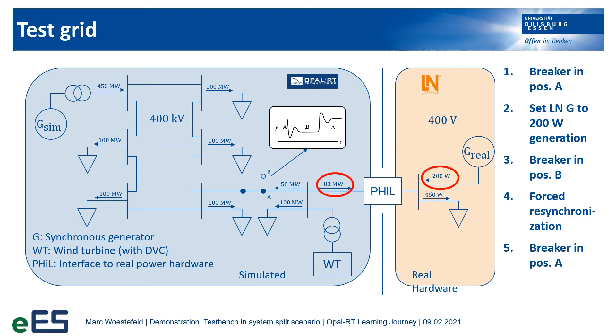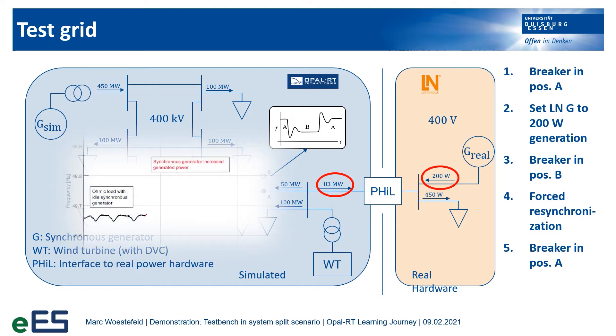Now let us increase the power in-feed from the real synchronous generator. Since the generated load is increased, the simulated load will be decreased, so the frequency will rise due to the mentioned P-f droop curve.